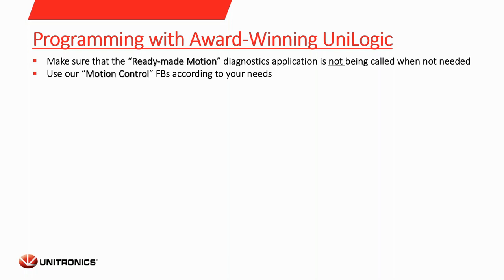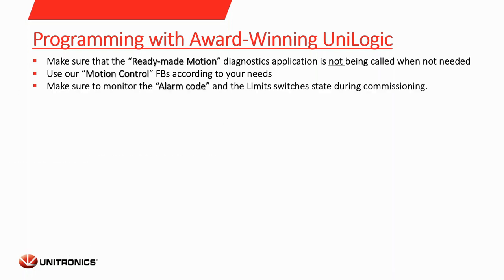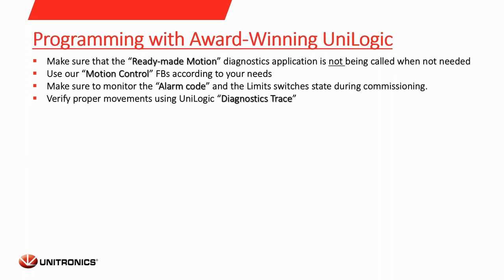After doing that, you can use our motion control function blocks according to your needs — it depends on your application. Please make sure when writing the code you monitor the alarm code on the axis and monitor the limits state during the commissioning. When you're close to the machine, you might skip this because if something happens you can see the error on the drive directly. But since you're not there, I highly recommend monitoring the alarm code and the limits state.